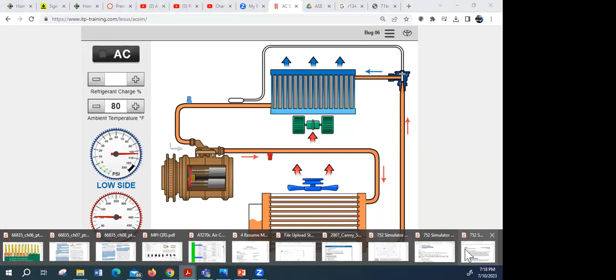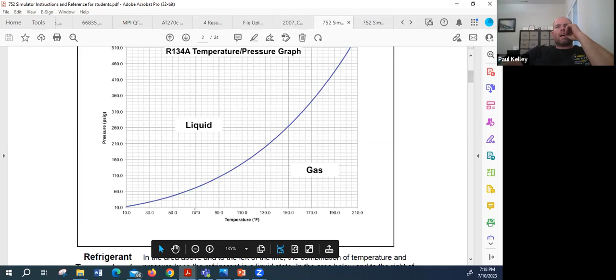Interesting, well I already see something a bit concerning. So it's 80 outside, okay. If we looked at this, if it's 80 outside, 70, 80, it should be at about... 60, 65, 70, 75, yeah, not even 80, probably around 80 something. All right, here it's 80 degrees, and I'm showing over 110 on the static.